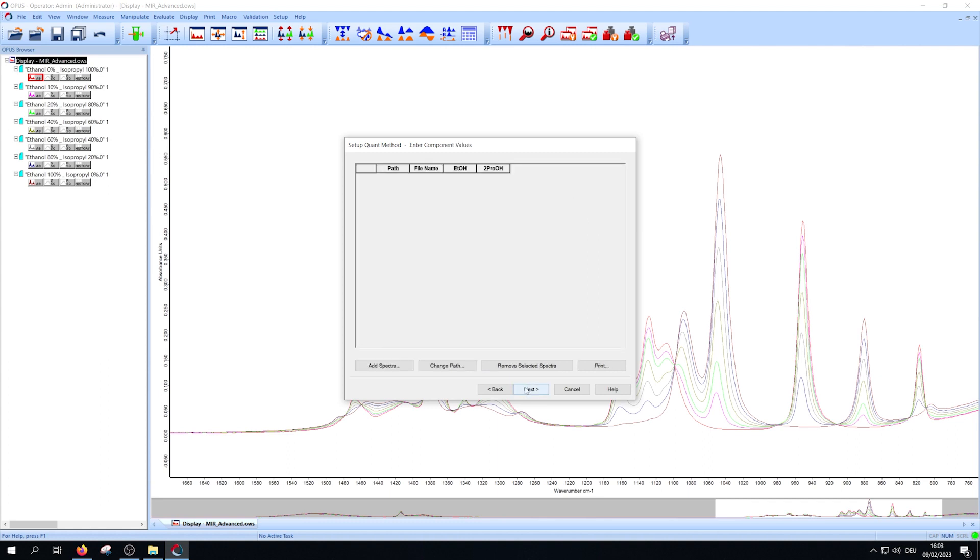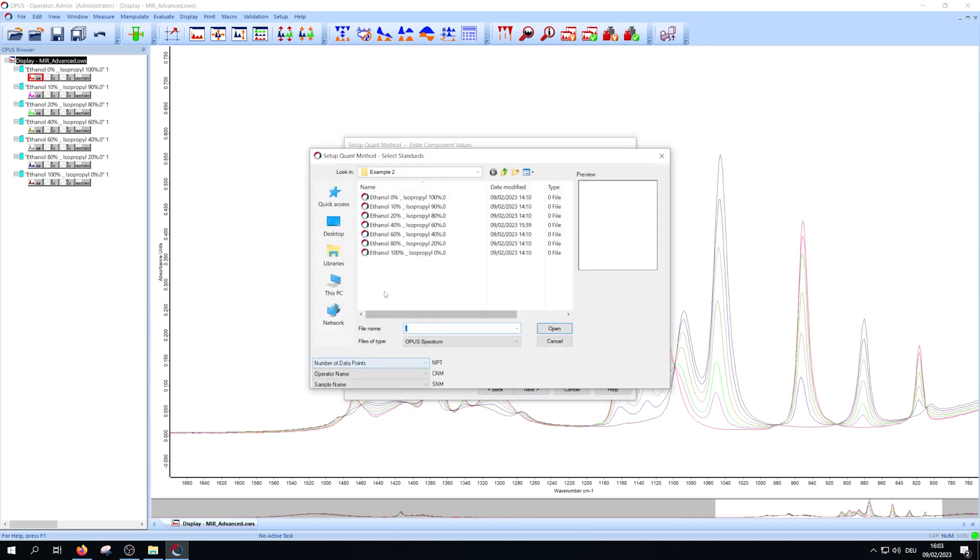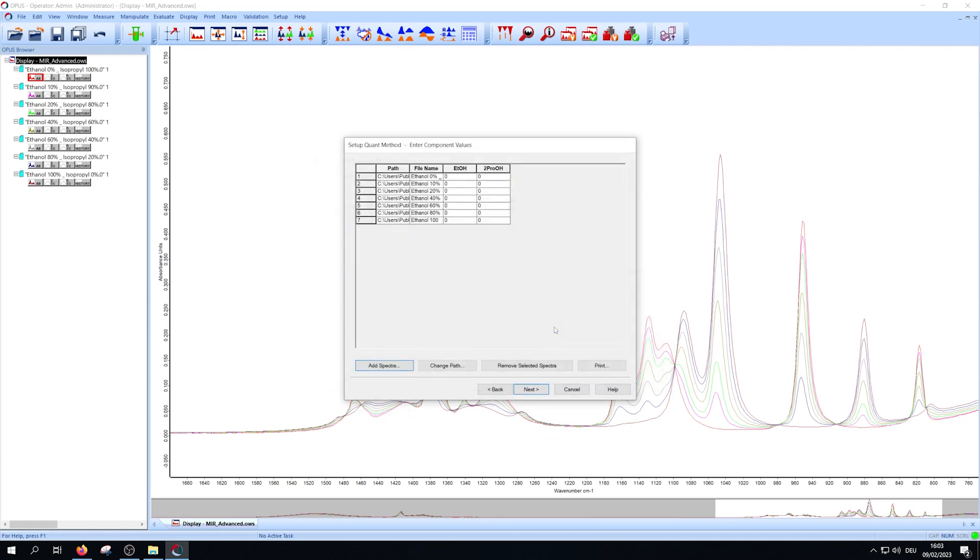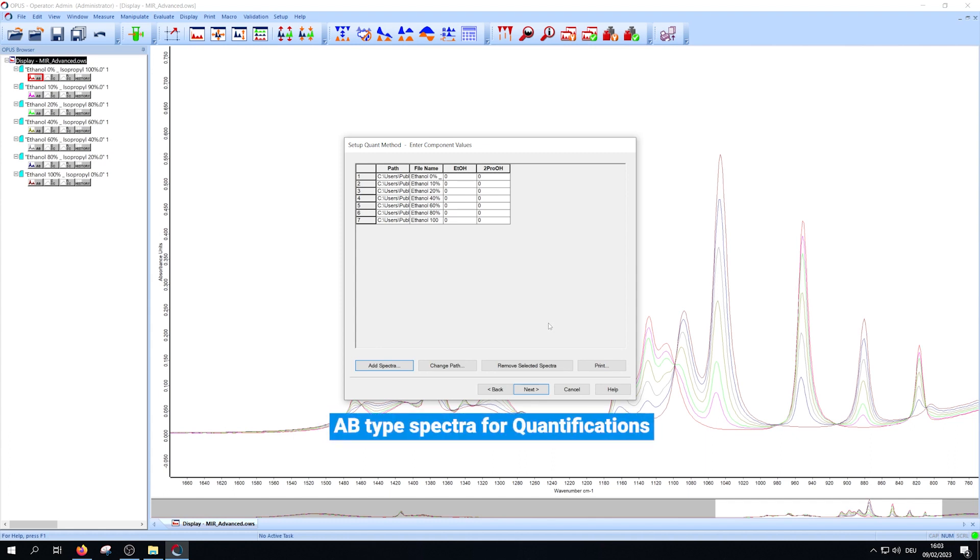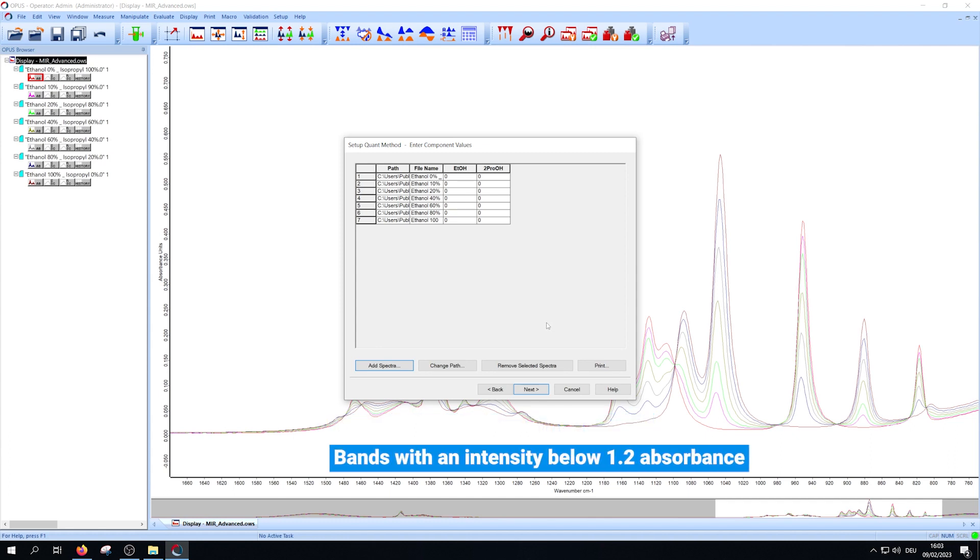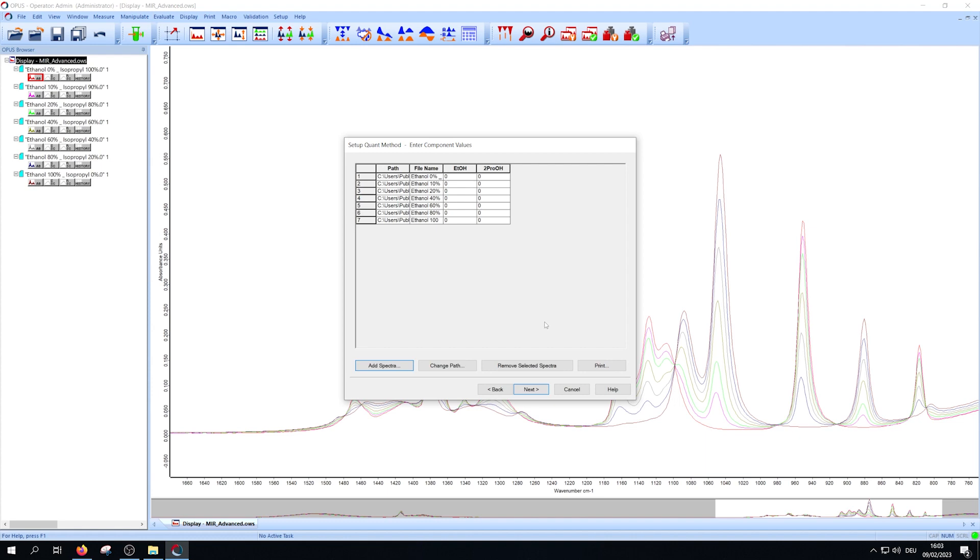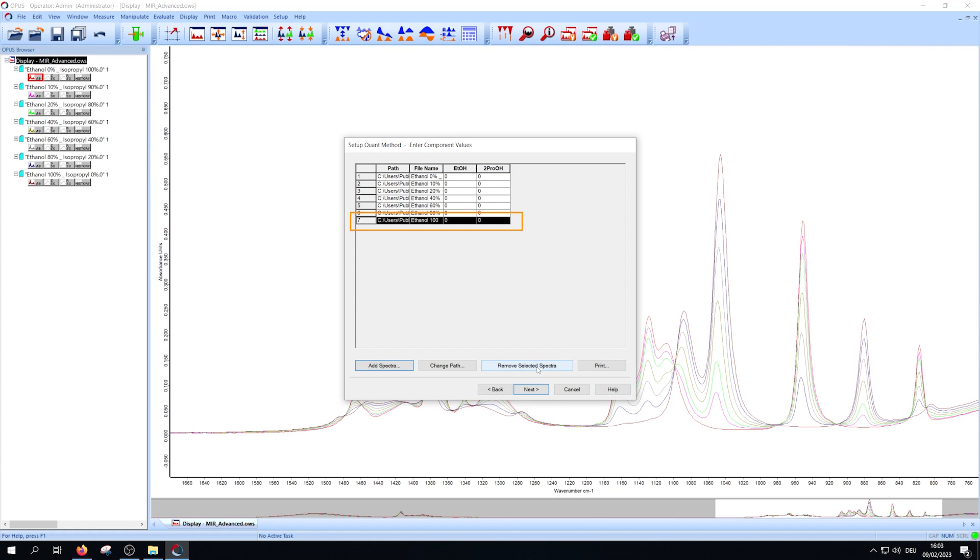In the next window you have to add the reference spectra. Press add spectra, select your files and press open. Typically you want to use B-type spectra for quantifications and bands with an intensity below an absorbance of 1.2. If you opened a wrong one you can select it and press remove selected spectra to delete it.